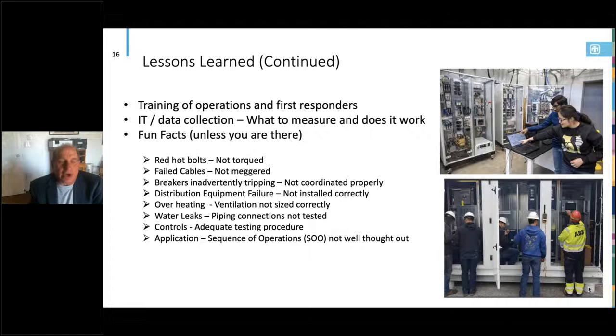But I've seen red hot bolts because we didn't torque, failed cables because they weren't meggered, breakers inadvertently tripping because they weren't coordinated, failures in equipment because they were not installed correctly. And I want to make a comment on that one: commissioning is not just for new systems. Every time you do maintenance on a piece of equipment, you should always do an abbreviated commissioning on that piece of equipment to make sure that you put it back together correctly.